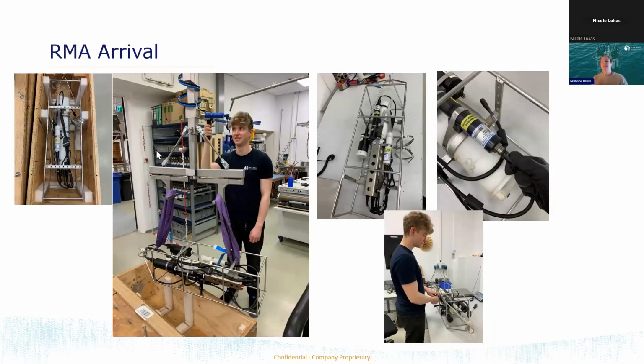So the check-in process here, here's an example of what this could look like. You've got a CTD here that's arrived in a crate. First thing we do is check what's arrived against what you've put on the RMA form, just to make sure that everything that you said you were sending in is actually in the box. There's no extra sensors. There's no additional things that we need to take care of. And then we make sure we're entering and tracking that information in the database that we use to track customer-owned equipment. But the first thing we do is just a set of bench checks to make sure that instruments are functioning, we understand what we've got, what we're looking at, and then we actually separate the built CTD system out into its individual components because we service and calibrate them separately.